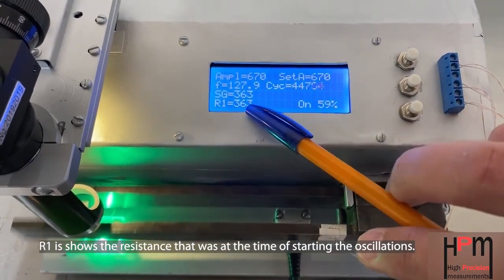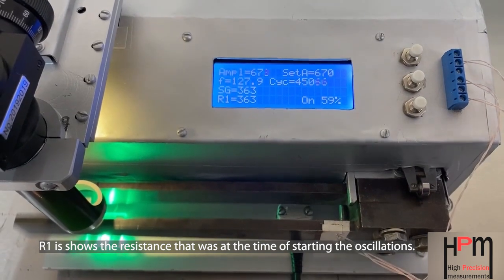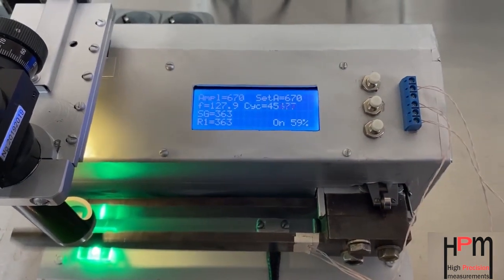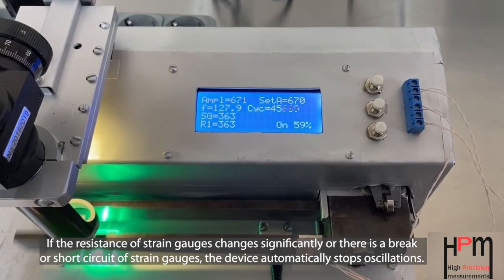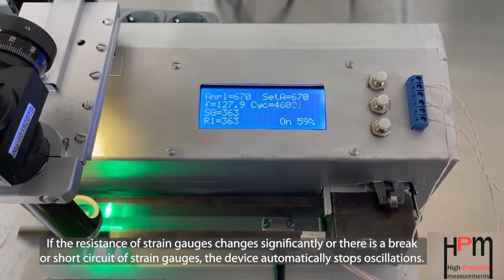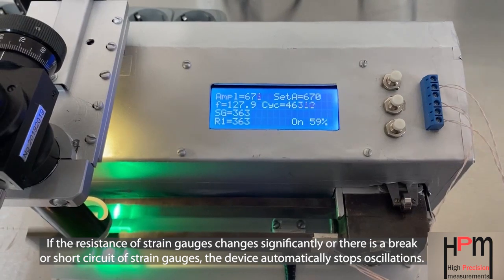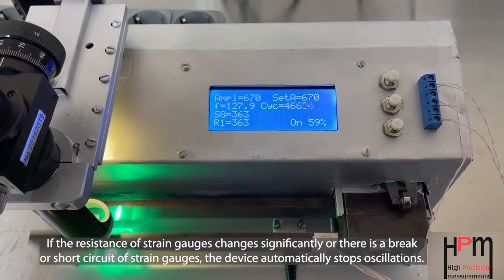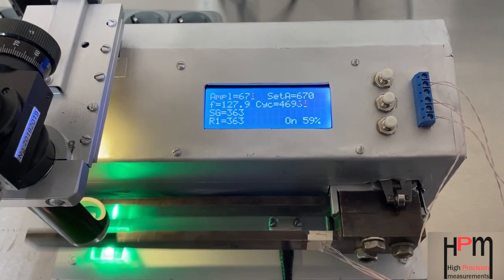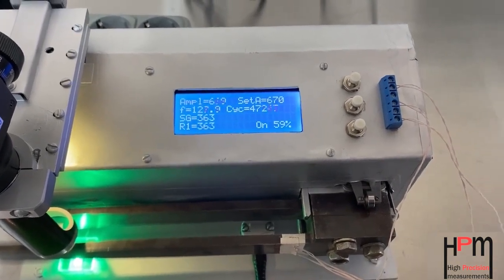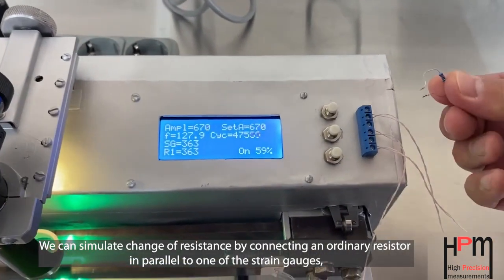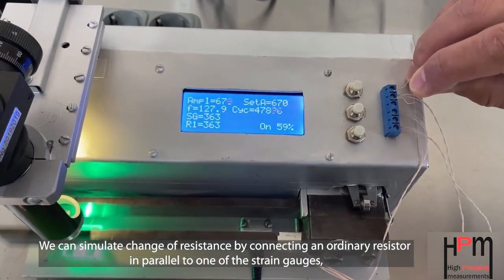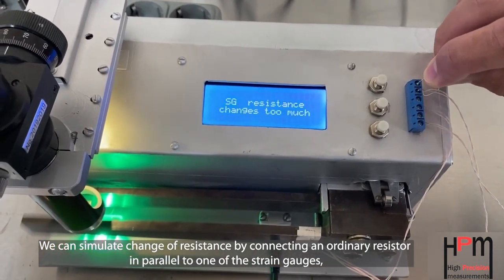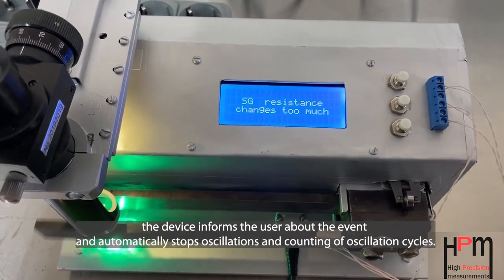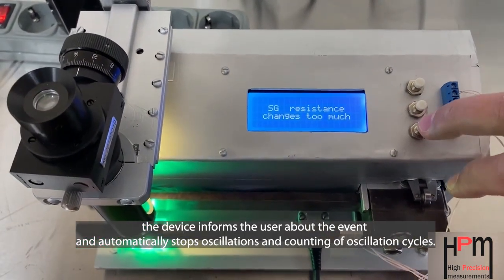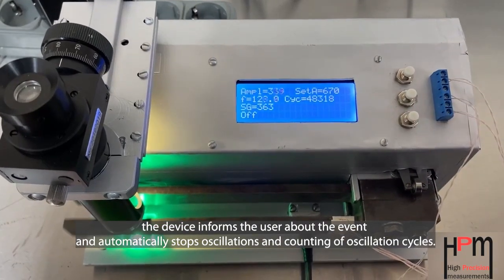R1 shows the resistance that was at the time of starting the oscillations. If the resistance of strain gauges changes significantly or there is a break or short circuit of strain gauges, the device automatically stops oscillations. We can simulate change of resistance by connecting an ordinary resistor in parallel to one of the strain gauges. The device informs the user about the event and automatically stops oscillations and counting of oscillation cycles.